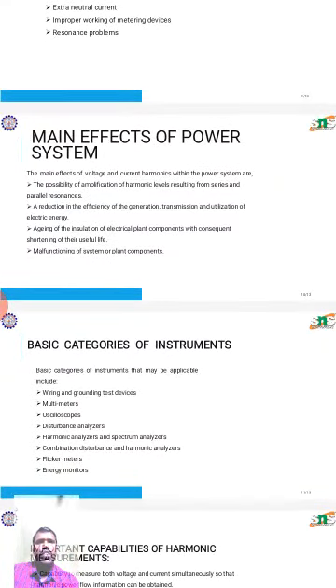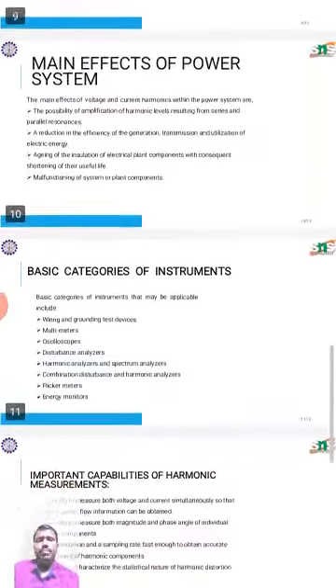The main effects of voltage and current harmonics on the power systems are: first one, the possibility of amplification of harmonic levels resulting from series and parallel resonance. Second one, a reduction in the efficiency of the generation, transmission and utilization of electric energy. Third one, aging of the insulation of electrical plant components with consequent shortening of their useful life. And fourth one, malfunctioning of system or plant components.